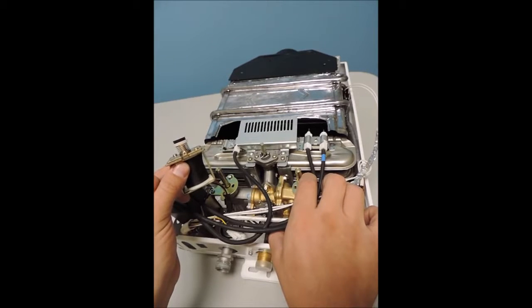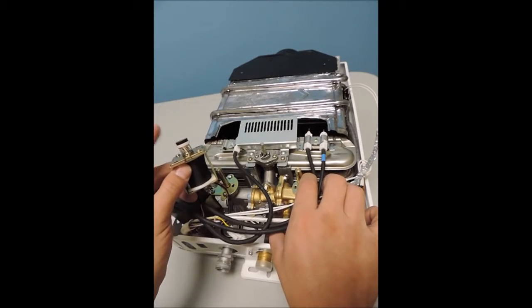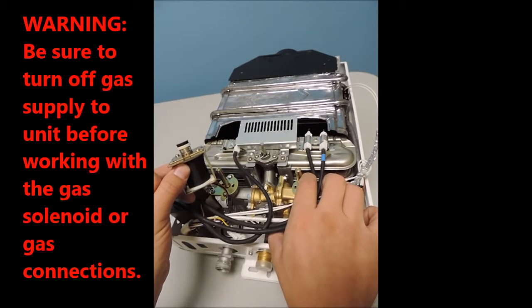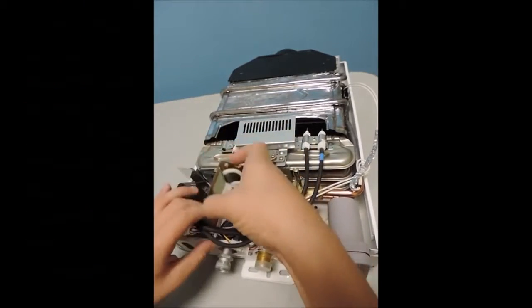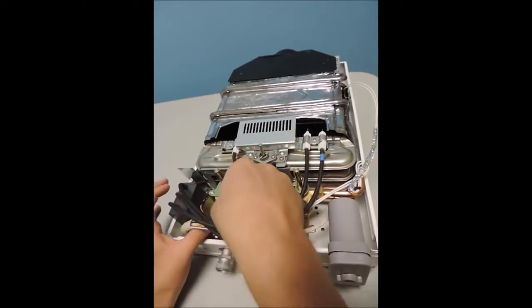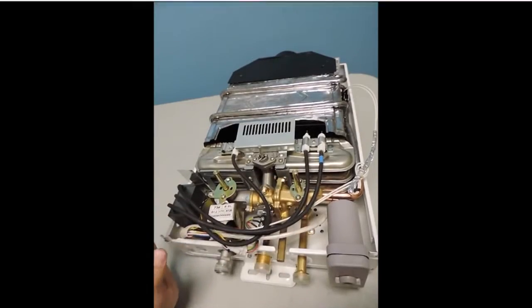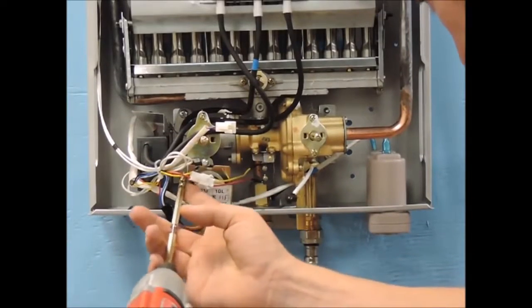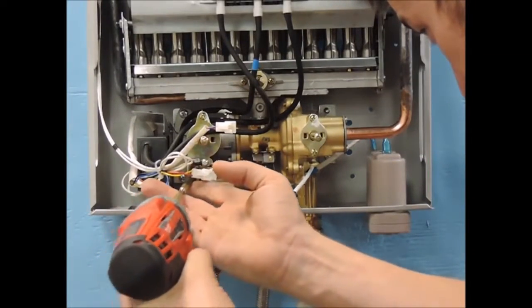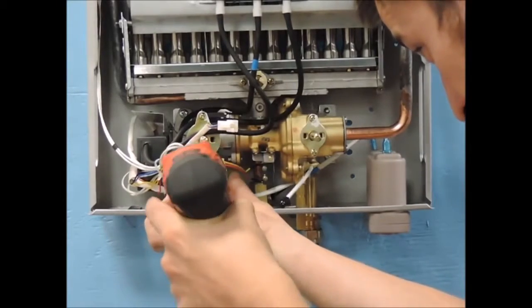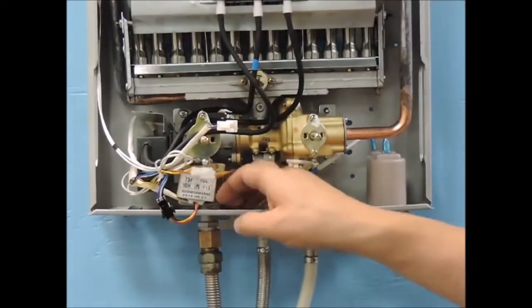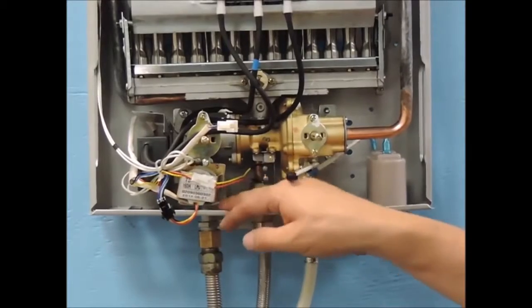Here we have shown the action of the plunger by removing the solenoid, but we do not recommend that you remove the gas solenoid unless you believe, based on the test, that it is not functioning properly and needs to be replaced. If you did remove the gas solenoid, then upon reinstallation, please make sure you did not lose the gasket that seals the connection between the base of the solenoid and the gas valve itself.